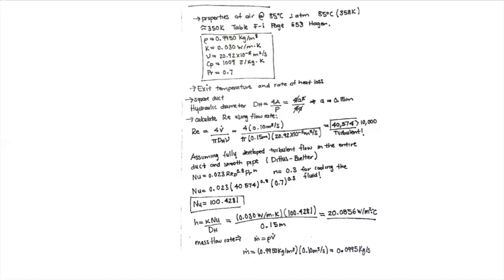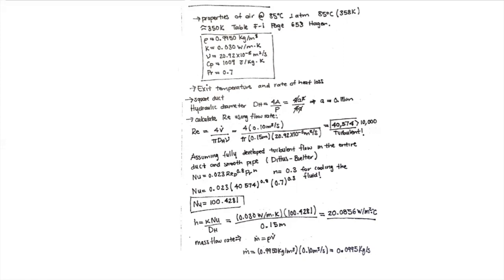I'm assuming a smooth pipe because the problem doesn't tell us the material or surface condition of the duct. If the problem specified a material like new stainless steel polished surface, you could get the roughness, calculate the relative roughness (roughness divided by hydraulic diameter), go to the Moody chart or use the Haaland equation to get the friction factor, and then use a Nusselt correlation that involves the friction factor correction. Since we don't know, I'll assume smooth pipe.